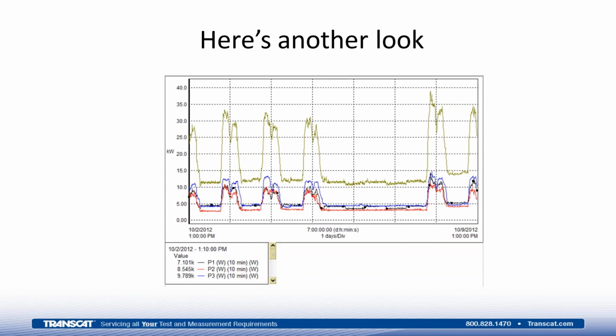Why does my building have a capacitor bank? I touched a little bit on that in the presentation also. The main purpose of a capacitor bank in a facility is to try to offset the motor loading that's in your facility. The capacitor bank is a leading power factor device. The motors are a lagging power factor device. And if I can incorporate a capacitor bank, in a lot of cases, I can offset the losses associated with the lagging of the motor power factor by applying capacitance to it. And applying the capacitance causes the power factor to move more toward the one that the utility likes.